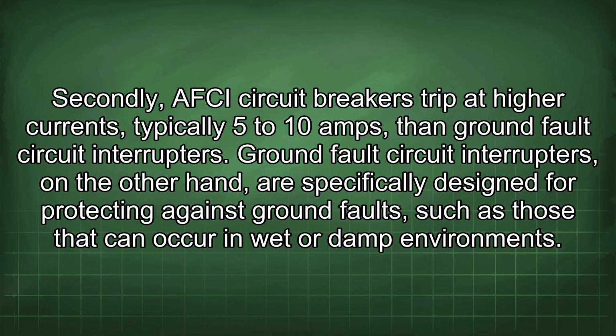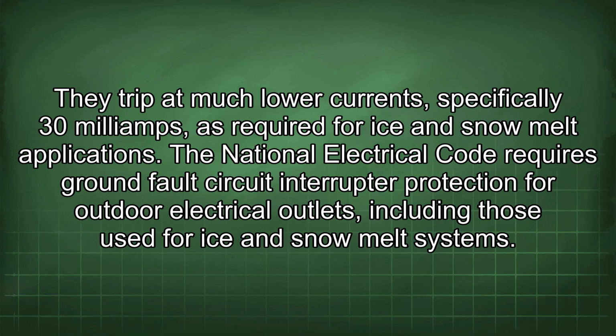Ground fault circuit interrupters, on the other hand, are specifically designed for protecting against ground faults, such as those that can occur in wet or damp environments. They trip at much lower currents, specifically 30 mA, as required for ice and snow melt applications.